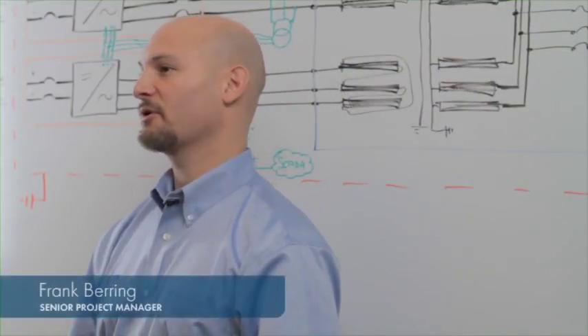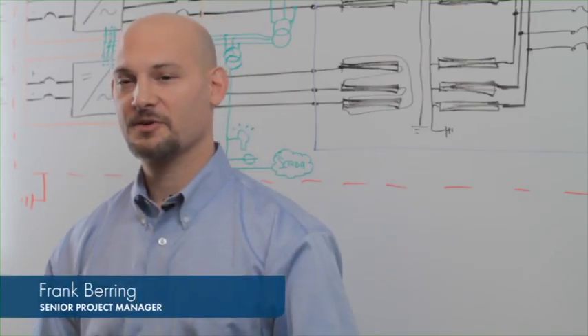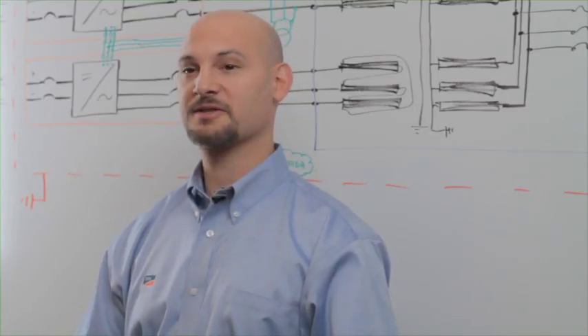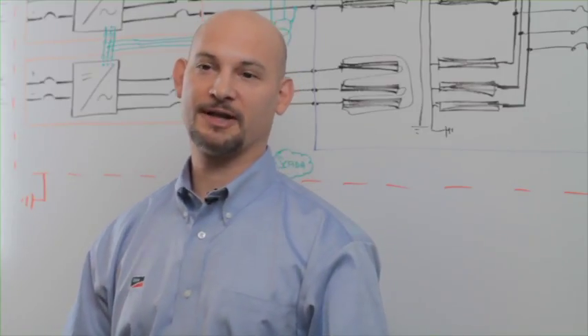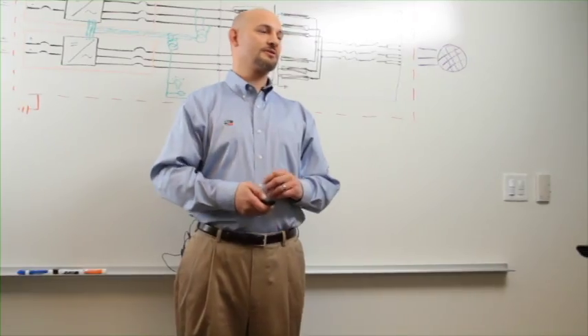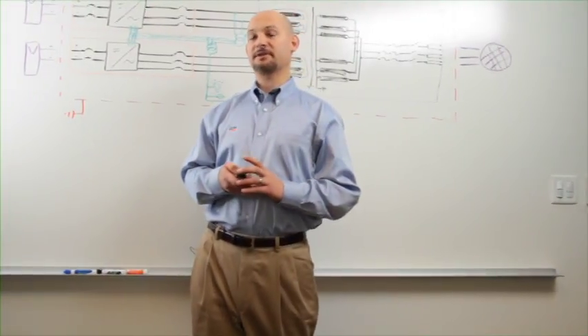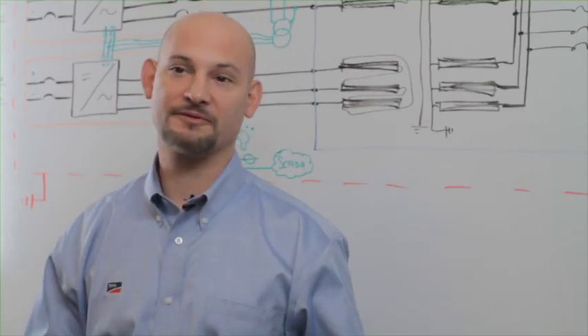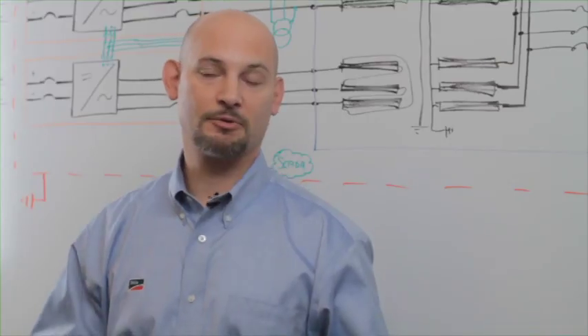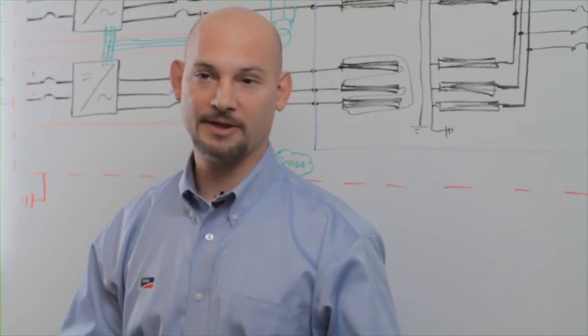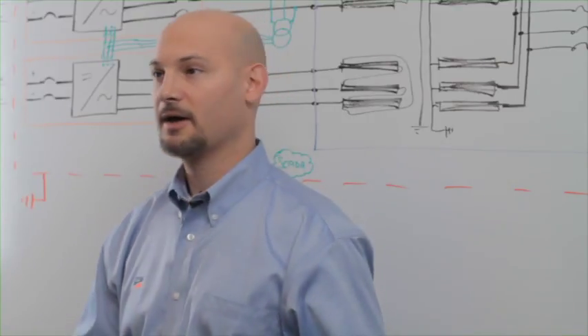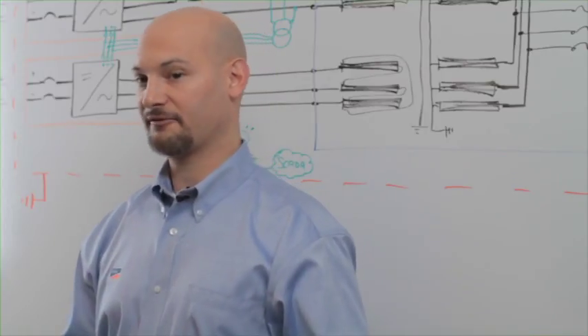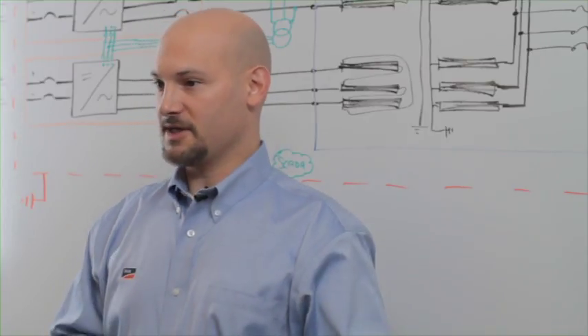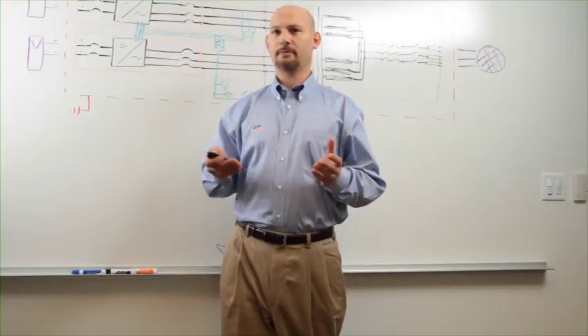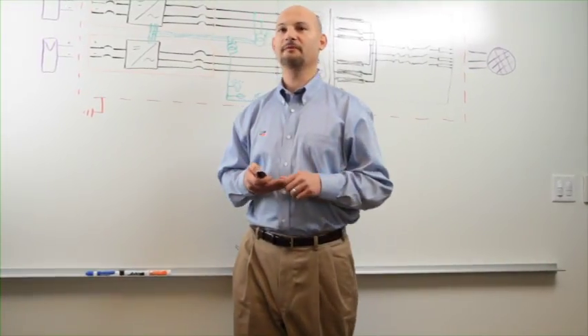Building on SMA's portfolio of central inverters, we're also able to offer our customers a higher level of value in an integrated solution for medium voltage interconnect applications. These solutions can be deployed in 600 volt arrays or 1000 volt arrays and can be deployed in a number of different power breaks, from a 1 megawatt block all the way up to a 2 megawatt block, for instance. So the power breaks are determinant on the power of the inverters.